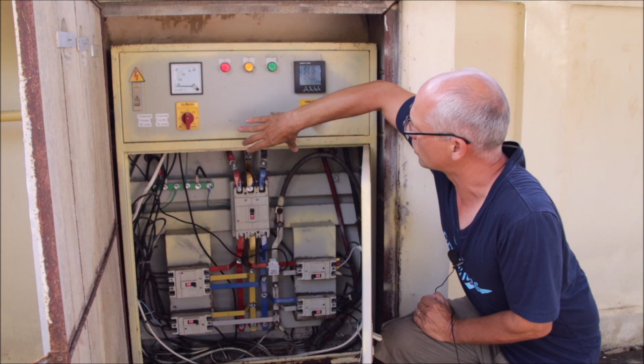This is a 250 amp three-phase breaker. The only thing inspected here was that these cables terminate into this 250 amp breaker, and that's it. The other thing checked was that the grounding bar is grounded to a grounding rod right next to the main distribution, connected with a 25 square millimeter copper conductor. That was it. So the utility inspector was interested up until here.